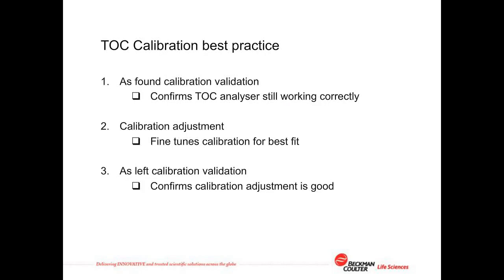When calibrating an instrument, best practice dictates that the current performance of the instrument be checked before any adjustment is made. This as-found calibration confirms that the instrument has been working within acceptable tolerances in the period of use. Then the instrument calibration should be fine-tuned to adjust it so that it reads as close to the certified standard values as possible to avoid long-term calibration drift. Having made this adjustment, calibration should be checked once more, validated against certified standards to make sure that the adjustment has left the instrument working accurately.